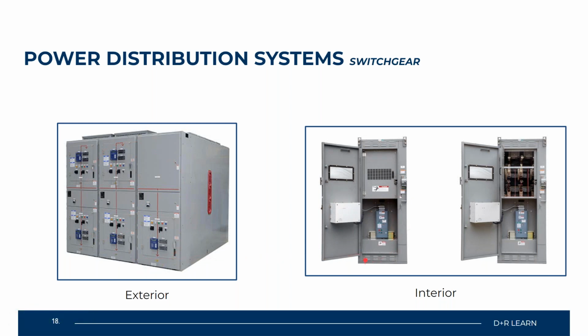And then on the inside, you're going to find any types of fuses that will be part of the system to allow it to operate the way that it needs to. So on your exterior, you're going to find any type of start, stop, hand, off, on, auto switches, and any type of LCD screens for quick access and reading of your electrical signals. And on the interior is where you will find the hardware of your electrical system for that piece of switchgear, whether that is fuses or other electrical equipment or components.